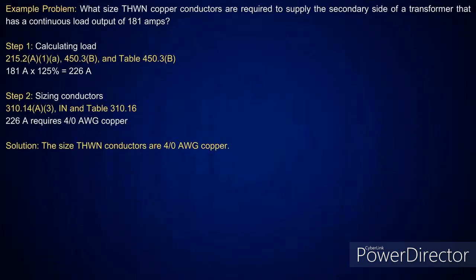All right. Now, this one is where we're going to size the copper conductors that supply the secondary side of a transformer that has a continuous load output of 181 amps. Now, if it is continuous, I have to take it at what? 125%. In this case, it's a feeder, so I'm going to apply 215.2(A)(1)(a), and that's where I get the 125%. So I take 181 amps at 125%, gives me 226 amps. Then I need a conductor for that. Well, I go over to Table 310.16, pick up the 75 degree C column. The next size above that's 230 amps, which is a 4/0 conductor.